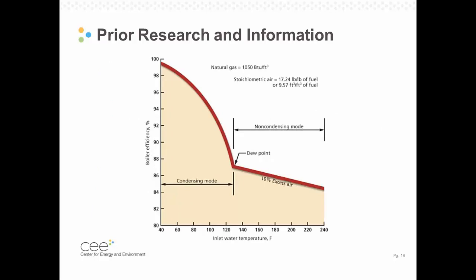This diagram shows that interaction between return water temperature and condensation points. So as you can see, the efficiency steadily increases when the return water temperature is between 240 and approximately 130. And then right at around 130 degrees, the efficiency really spikes up. And so that is the dew point, and that's where you can see this dramatic increase in efficiency. So it's important to try and get below that 130-degree mark in order to effectively utilize the efficiency of these pieces of equipment. However, it's also important to get that return water temperature as low as possible. So as you can see, even below 130 degrees, there's still quite a bit of room for improvement. So this is all to say that that return water temperature being below 130 matters a lot, and we want to try and figure out how we can maximize that while still maintaining comfort within these homes.